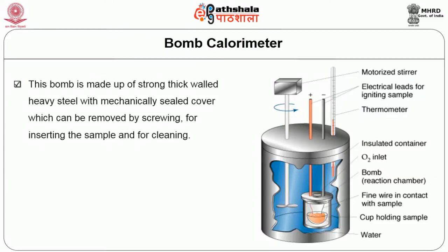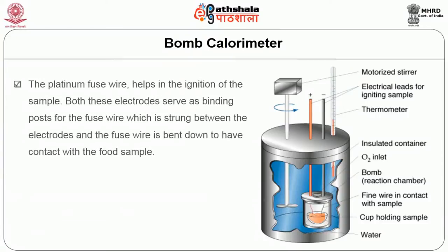The bomb is made of strong thick-walled heavy steel with a mechanically sealed cover which can be removed by screwing for inserting the sample and for cleaning. There are two electrodes attached to the underside of the double-walled head of the cover. The platinum fuse wire helps in ignition of the sample. Both electrodes serve as binding posts for the fuse wire, which is bent down to have contact with the sample. The stirrer is attached to the lid, along with the cup for holding the food sample to be analyzed. The thermometer is specially designed and supplied along with the instrument.